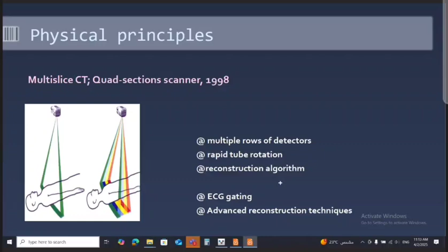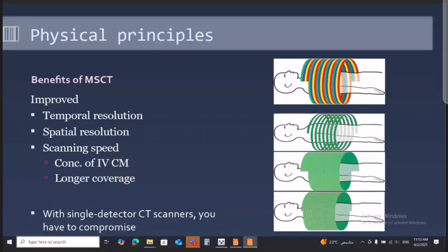The adding factors are the addition of ECG gating and advanced reconstruction techniques, and here CT coronary angiography entered the field of imaging in CT. The benefits of multi-slice CT are improved temporal and spatial resolution and scanning time. We can acquire a large number of images in a very short time, and we don't need to increase the slice thickness, create gaps, or prolong the time for acquisition. And so we could proceed to perform CT coronary angiography with the multi-slice CT.